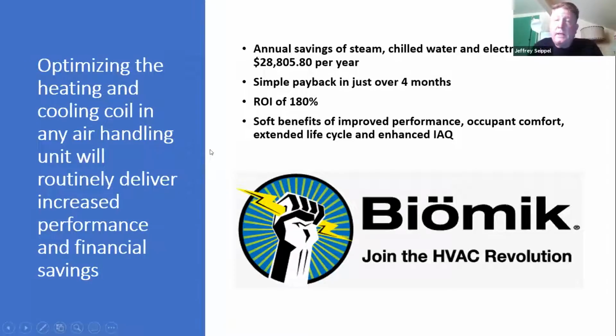A quick case study. This is a blind third-party case study at the University of New Mexico. It was performed by one of my licensees, Aquis. It was done unbeknownst to them by the university energy manager. And the energy manager looked at 3 energy inputs. He looked at steam through a heating coil. He looked at chilled water through the cooling coil, and he looked at electricity loads for the fans that drive the air.